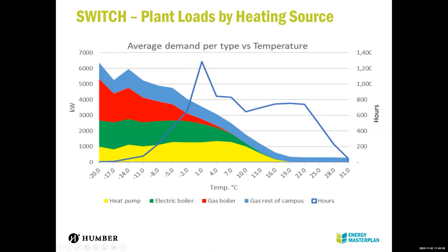As you get colder, those gas boilers take a much higher proportion of the overall heating load. But since most of our hours are in the middle range of the chart, we don't need to use much gas most of the time. And that's how we get that 70% drop in overall natural gas use.